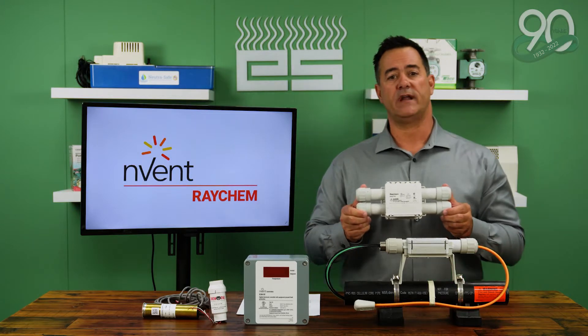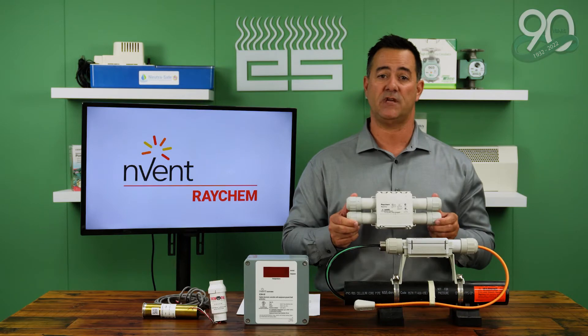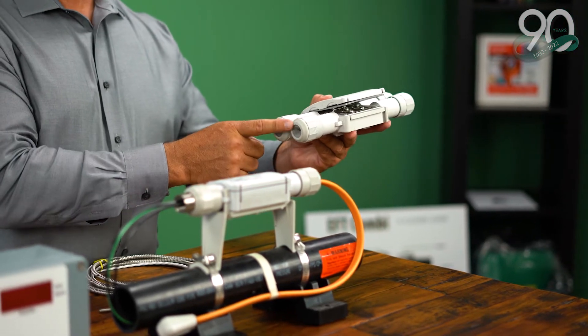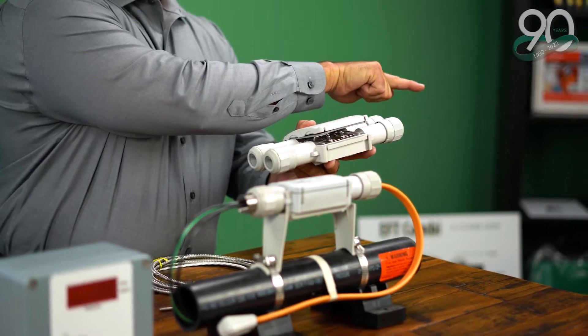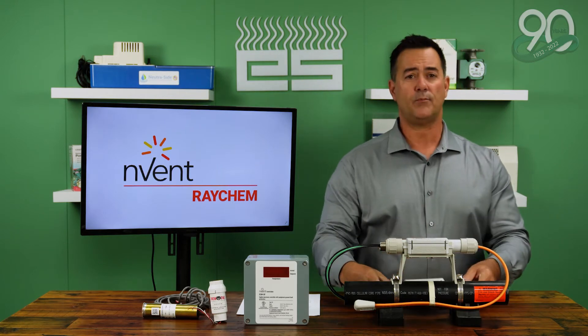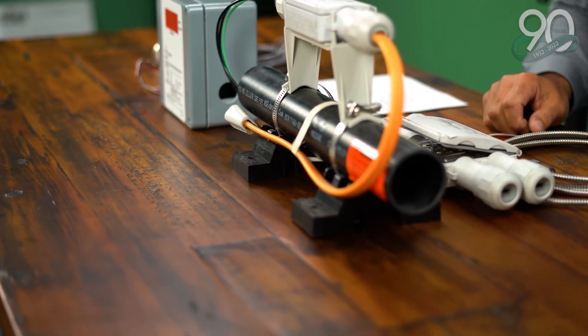This component here is called the RayClic T. It's a T connection used for branch lines within the heat-trace circuit. We would still run off of the RayClic PC originally, but then take the cable at a branch line and tie into the RayClic T. This line would then continue through the other side of the T, allowing a branch line to be used to continue off. All branch lines and regular heat-trace lines are then capped with a termination cap known as an end seal.